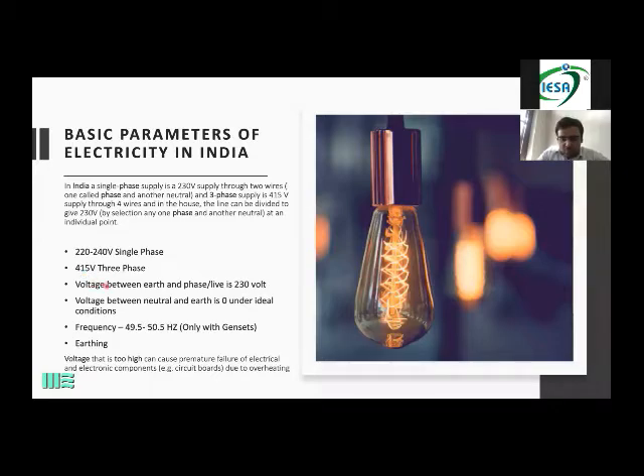The third thing is, now I told you that from neutral to phase, if you check, the voltage is coming. Now the voltage between the earth and the phase, the live wire. The earthing wire is always on the outside of the box. If you take a multimeter and put it on earth and on any color, red, yellow or blue, you will always get 230 volts. It could be between 220 to 240. So these parameters also need to be checked.